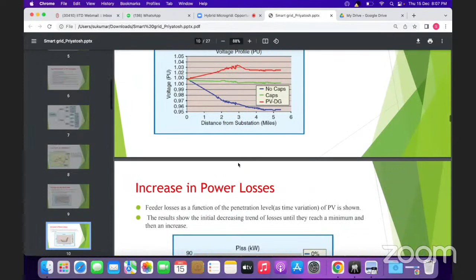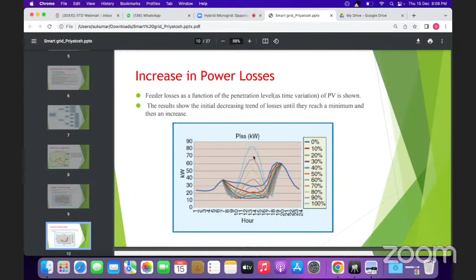Grid-integrated solar systems also increase power loss, particularly in the afternoon period. In the normal scenario, with no solar injection, the blue curve is the loss, but this curve becomes very peaky when solar gets integrated and goes beyond around 30%, which is the base power of the distribution transformer, and you will see the loss increases.